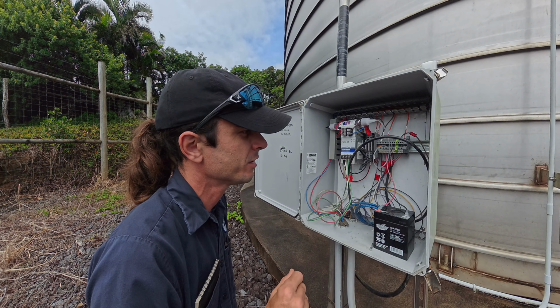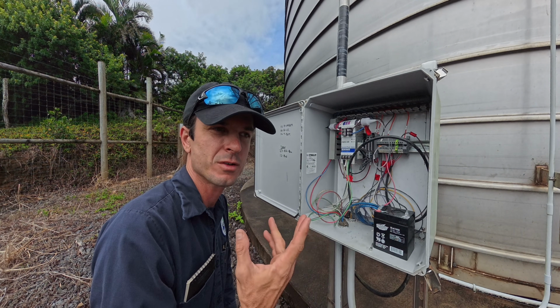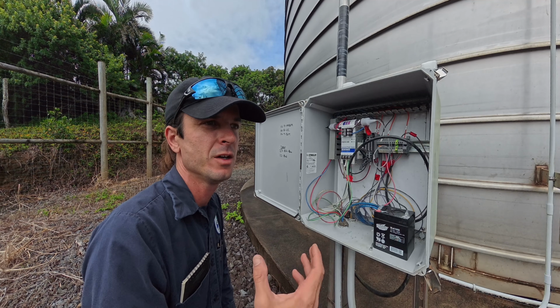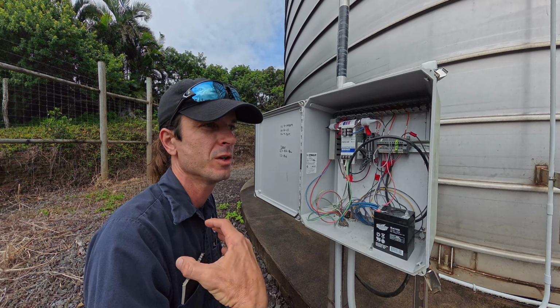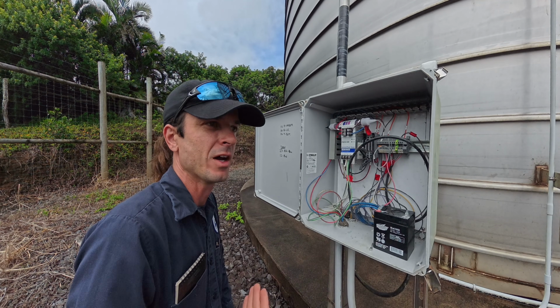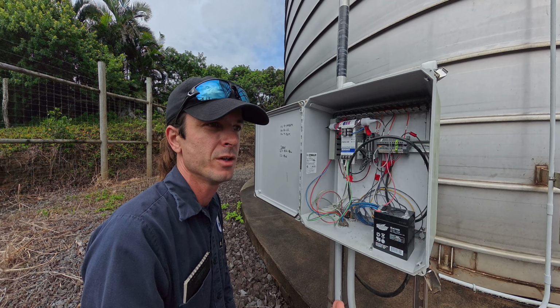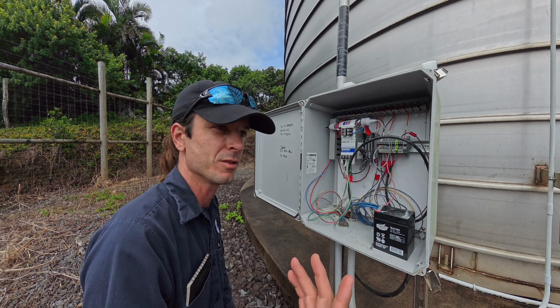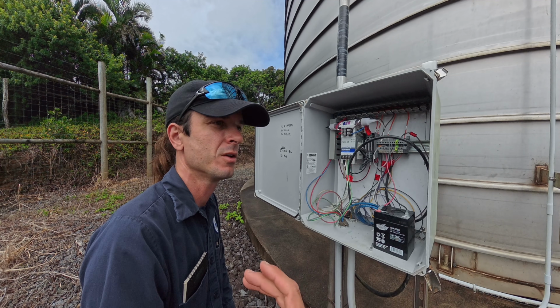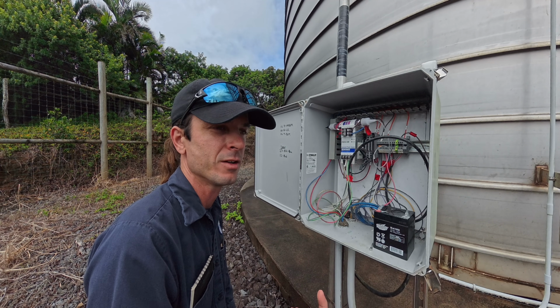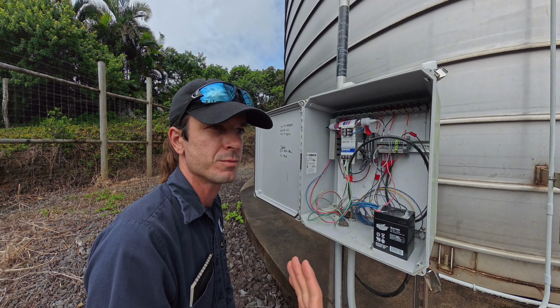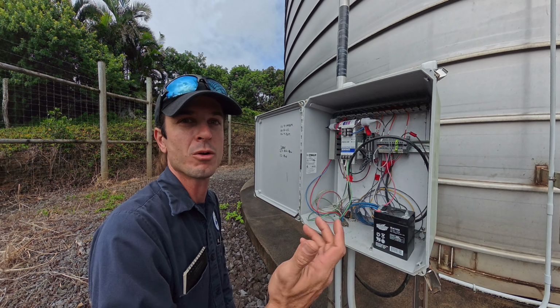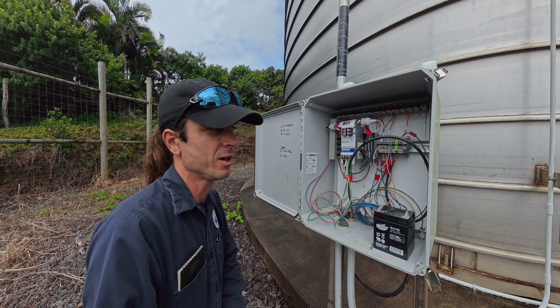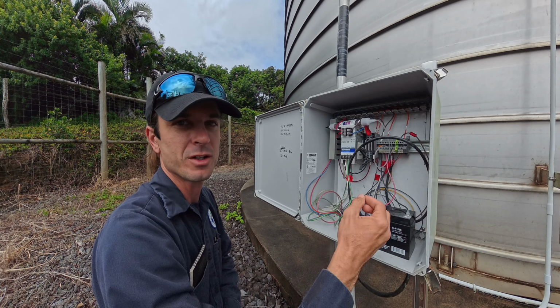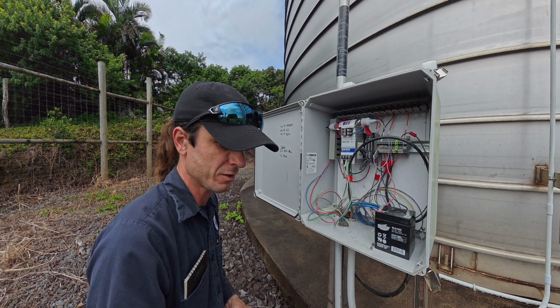Before I put a new one in, I'm just going to disconnect the transducer, test it with my Fluke 789 using my own 24 volts, just to see if I have a healthy signal from the transducer. If there's no healthy signal from the transducer, there's no sense in throwing in another fuse because it'll either pop again on overcurrent or a healthy fuse won't fix a broken transducer. So let's get the 789. We'll connect to these 2 wires here and we'll see what the transducer signal is.